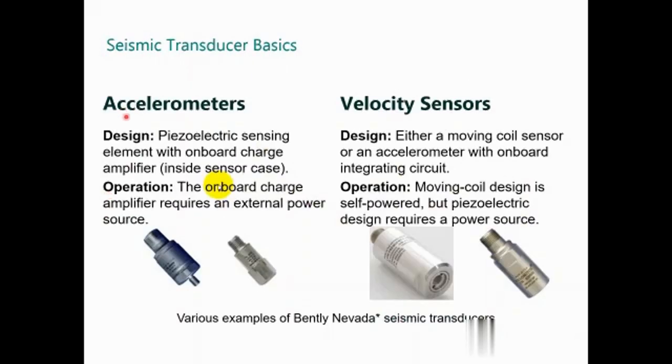The accelerometer is a piezoelectric sensor and the output is proportional to acceleration of the vibration. This requires an external power supply. We have two designs: the very old that requires external amplifier and the new one includes internal amplifier.